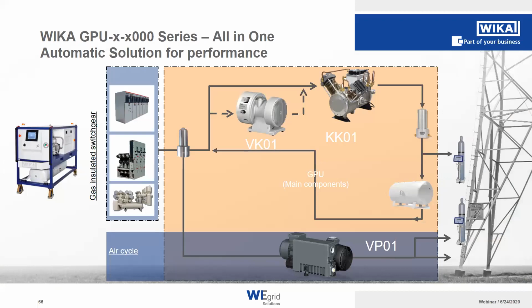So after I introduced you to these three main components, you see on this chart how they are laid out in the GPU. We can see that from the gas insulated switchgear, we run the gas flow through a particle filter, which is a smaller filter at the beginning of the cycle. Then we bypass the vacuum compressor, if not needed, into our SF6 compressor, which pushes the gas flow through another filtering unit, which is mainly for drying the SF6 gas, into our internal storage tank, or it could go to an external source.